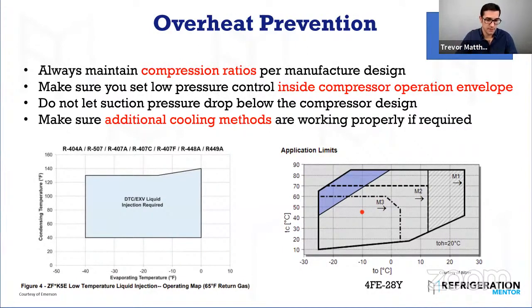And then I see 60% of you are saying dirt in the system. Exactly. Dirt in the system, a piece of copper, you're reaming out the copper and it makes its way back to the compressor and it causes a spot burn. Or you get a slug that happens, it breaks a piece of the suction reed and it goes into the windings. So I got a question here.